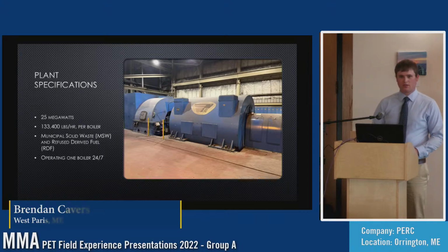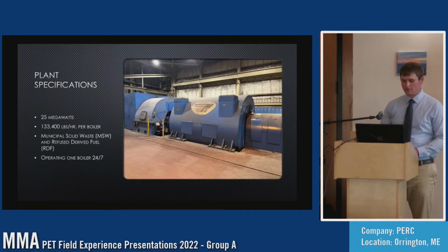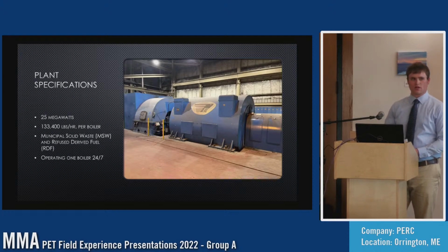There's one General Electric turbine and generator set, capable of producing 25 megawatts of power. We have 2 boilers, each capable of 133,400 pounds per hour of steam. On site, we receive municipal solid waste, which is ground up through grinders and turned into refuse-derived fuel. This plant only runs one boiler 24/7 and keeps the other on standby.